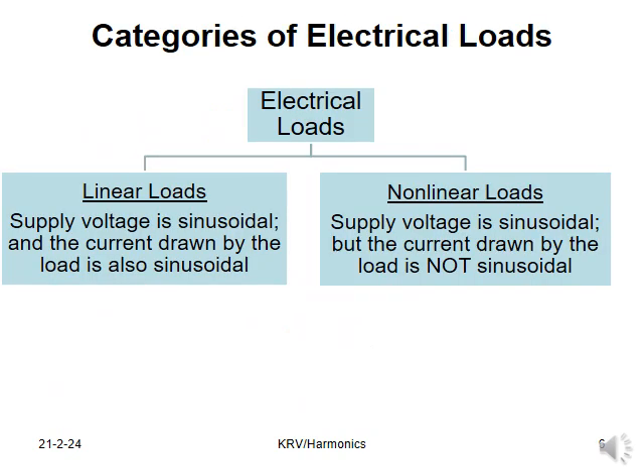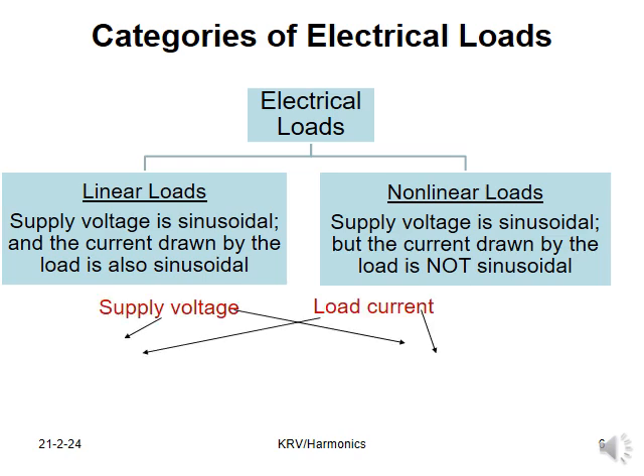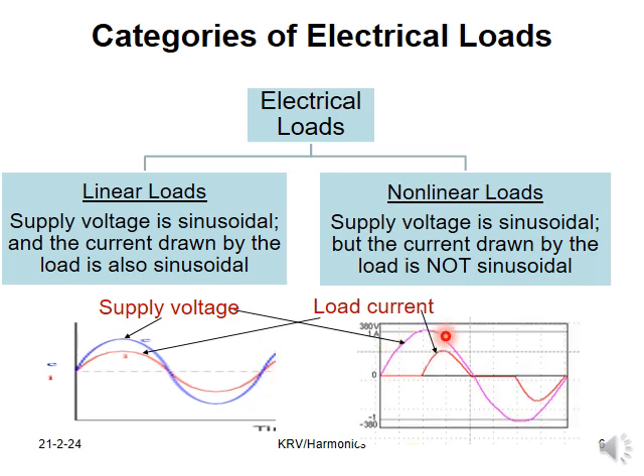We can categorize the electrical loads into linear loads and non-linear loads. In linear loads, the supply voltage is sinusoidal and the current drawn by the load is also sinusoidal. In non-linear loads, the supply voltage is sinusoidal but the current drawn by the load is not sinusoidal. These are shown in the figures below. In a linear load, the supply voltage is sinusoidal. The current drawn by the load is also sinusoidal. In a nonlinear load, the supply voltage is sinusoidal, but the current drawn by the load is not sinusoidal.